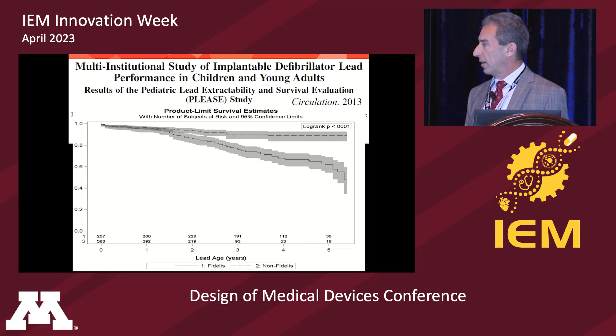75 or 80% of them received thin single coil leads, of which 35% of them failed. Again, as you get younger, you have a higher incidence of using the thin lead. They were chosen by the implanter, and there was a higher failure rate of those thin leads. So a disproportionate effect on children. And when you compare the thin leads to non-thin leads, you can see in this Kaplan-Meier survival curve, the failure rate was significantly higher in the thin leads compared to the non-thin leads.